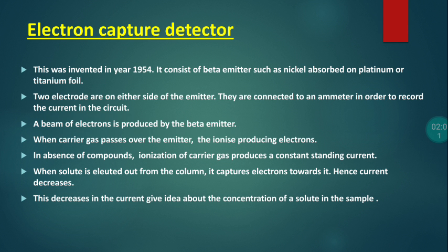The effluent from the chromatographic column is exposed to slow electrons generated by the ionization of the carrier gas, which is either argon or nitrogen, by a constant flux of beta rays from a radioisotope. When electron capturing molecules in the effluent gas capture an electron, the result is the formation of negative ions of much higher mass and consequent reduction of current flow.